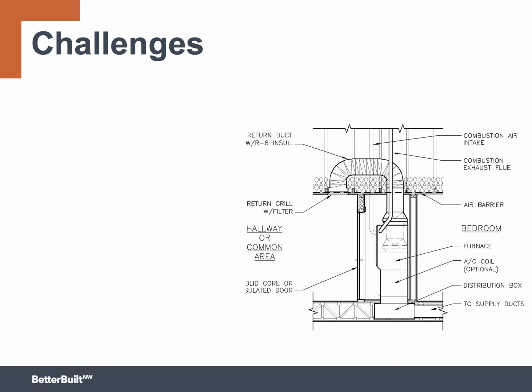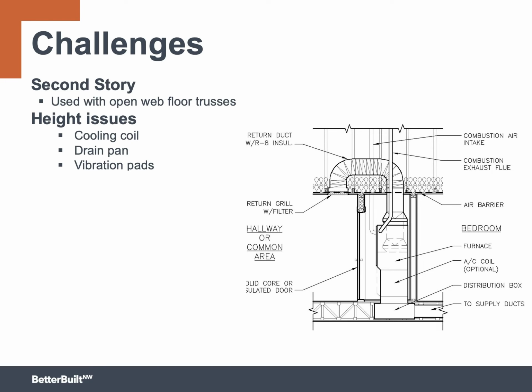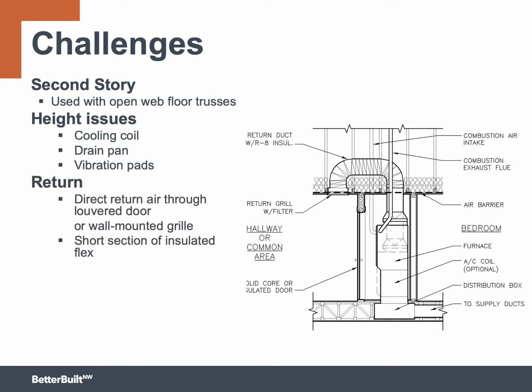Locating the furnace inside the conditioned space presents several challenges. Let's look at these along with some potential solutions. The furnace will consume some floor area. Be sure to allow enough space to access filters, make repairs, and meet all code required clearances. Don't forget the height requirements or the extra vertical space for a cooling coil, a drain pan, and a filter rack. It's possible to run the return directly through a louvered door or through a very short section of duct that goes through the attic space.